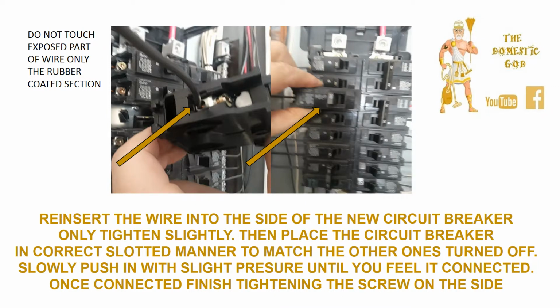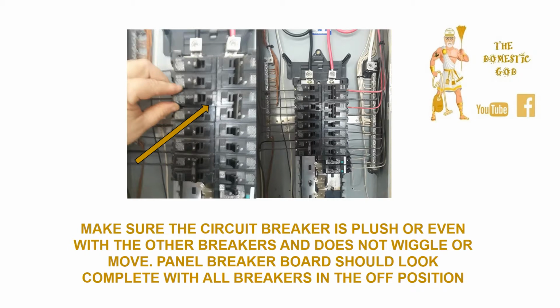Now take the new circuit breaker and reinsert the wire into the side of the new circuit breaker. Only tighten slightly with the screwdriver. Then place the circuit breaker in correct slotted manner to match the other ones turned off. Slowly push in with slight pressure until you feel it connected. Once connected, finish tightening the screw up on the side. Make sure the circuit breaker is flush or even with the other breakers and does not wiggle or move. Panel breaker board should look complete with all breakers in the off position.